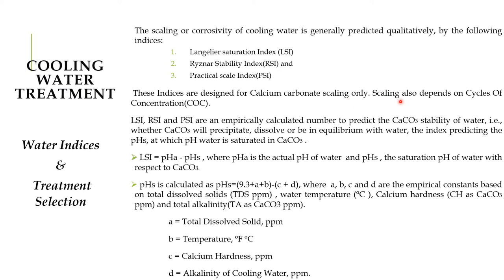These indices are designed for calcium carbonate scaling only. Scaling also depends on Cycle of Concentration (CoC). The Langelier Saturation Index, Ryznar Stability Index, and Practical Scale Index are empirically calculated numbers to predict the calcium carbonate stability of water — whether calcium carbonate will precipitate, dissolve, or be in equilibrium. The index predicts the saturation pH at which water is saturated in calcium carbonate.